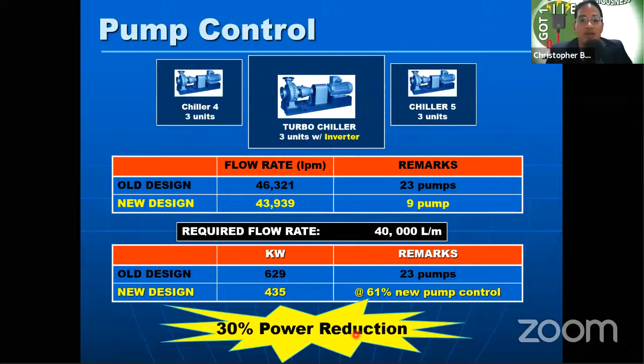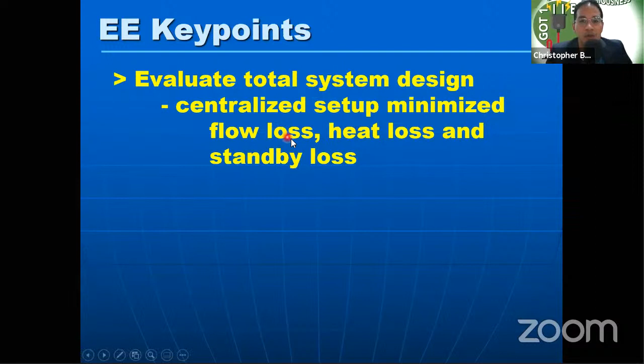So some key points on design optimization: always evaluate the total system design, as Engineer Pabilona mentioned earlier, you need to check the design. Use a centralized setup to minimize flow loss, heat loss, and standby loss. Use alternative equipment - in our case, we used turbo chillers instead of air-cooled chillers, and optimized control using frequency inverters and an automated control system.